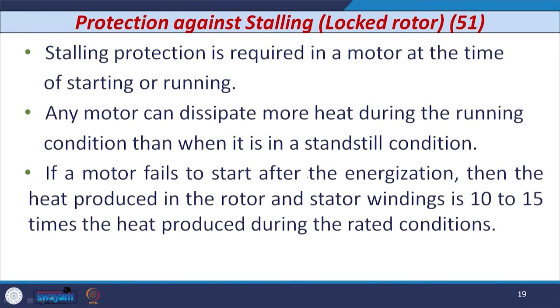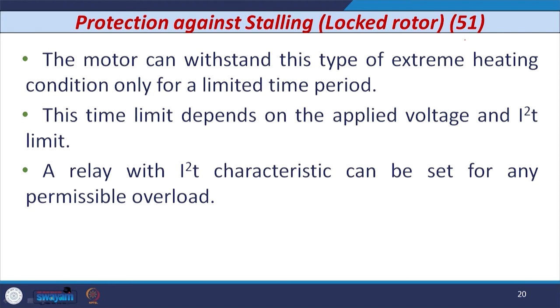Let us consider protection against stalling or locked rotor. The relay number given is 51. Stalling protection is required at the time of starting or running of the induction motor. Any motor can dissipate more heat during the running condition compared to when it is in standstill. If the motor fails to start after energization, the heat produced in the rotor and stator winding is 10 to 15 times the heat produced during rated conditions.